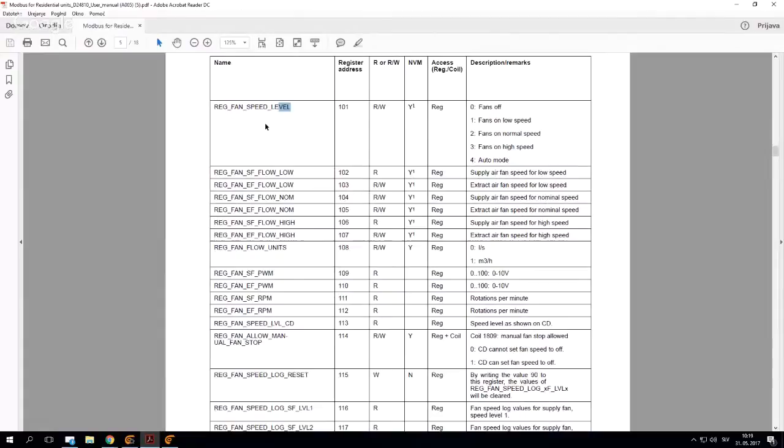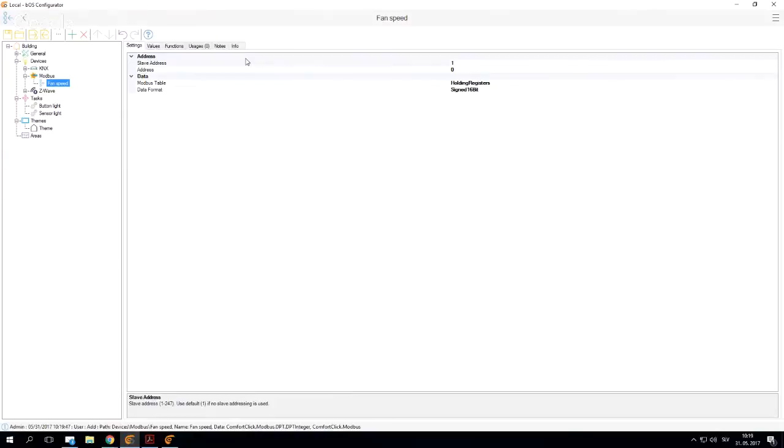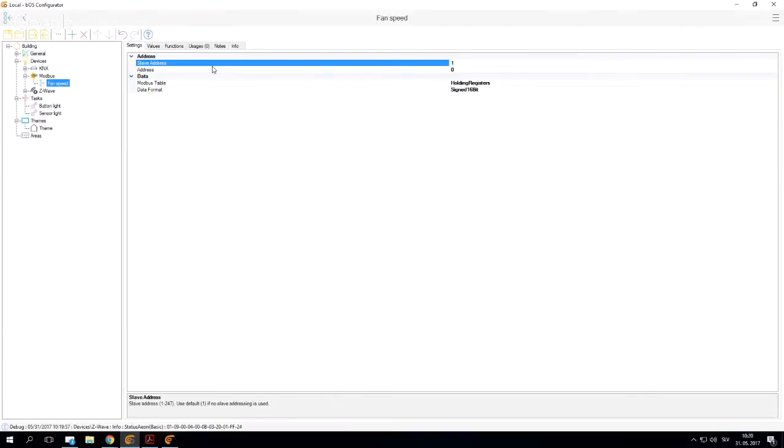Of course, I need my manual to import this. Since this is a simple fan speed device, I'm going to go to Modbus and add an integer and name it fan speed. My integer opens up and I can see that I have multiple things that I can configure here. I can configure our slave address, which is if I have multiple devices.